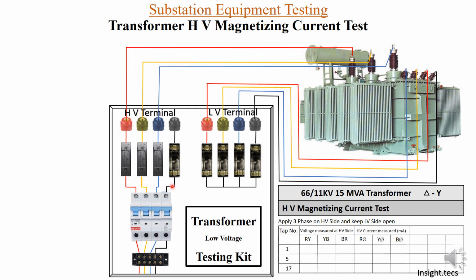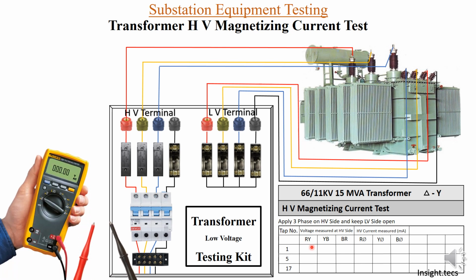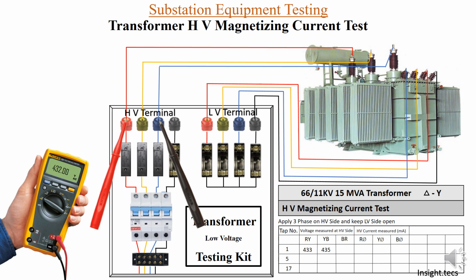Let us close all the fuses and turn on the MCBs. What we will measure first is the voltage on the HV side for R and Y phase. Using the multimeter we will measure the voltage. The voltage is 433 volts, so we will write 433 here. Next, for Y and B phase, it is 435 volts, so we will write 435 volts here. Similarly, for B and R phase we have 432 volts.